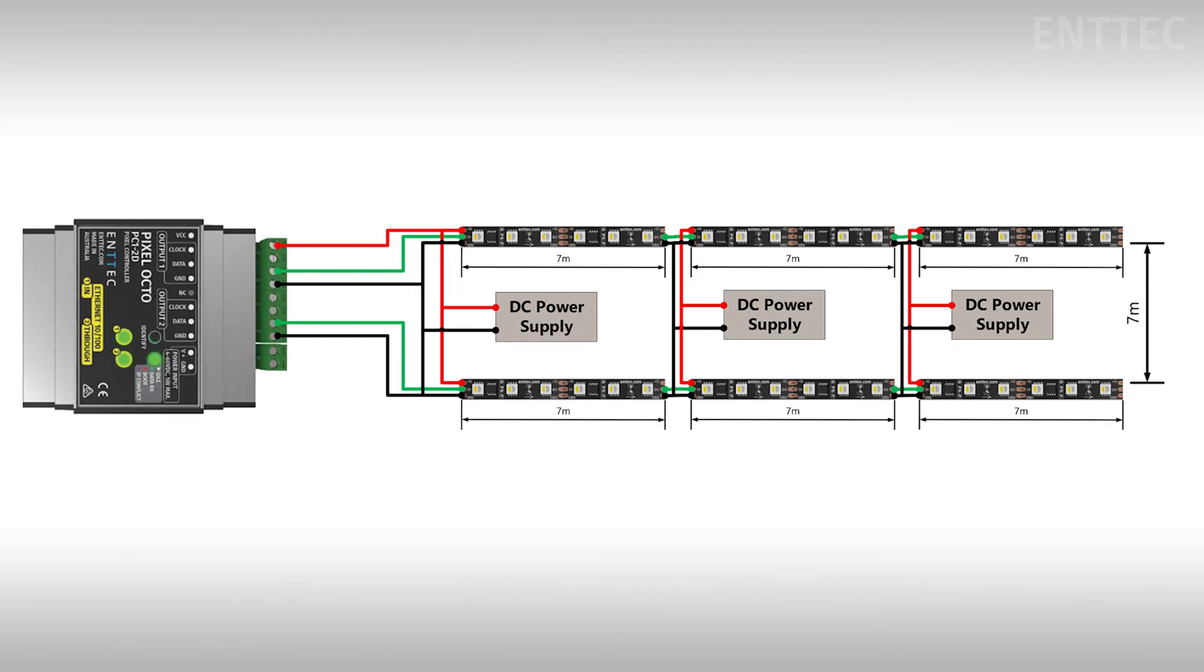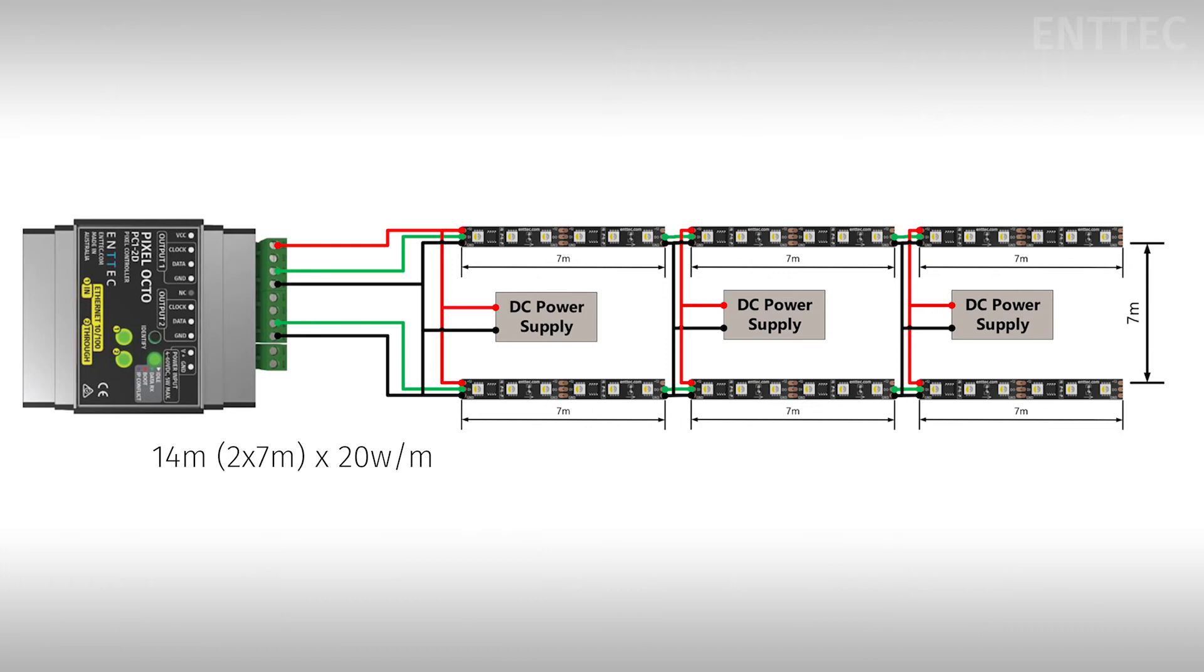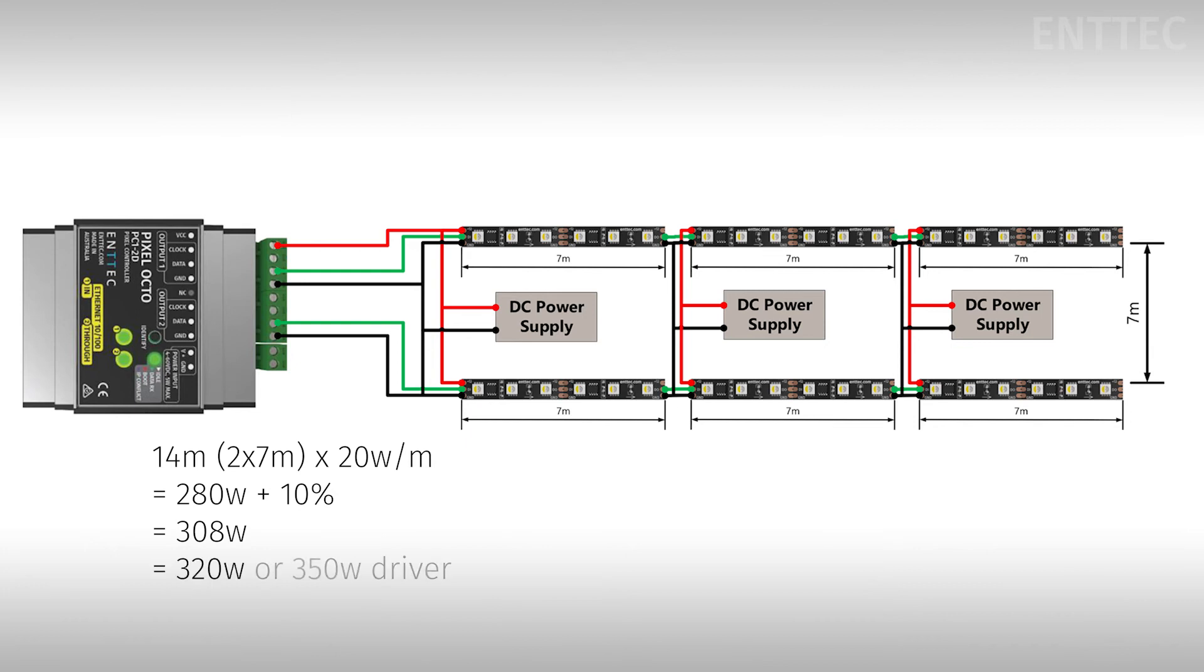Each power supply will be powering a total of 14 meters split across two separate 7 meter lengths. At approximately 20 watts per meter we can calculate that each DC power supply needs to provide at least 280 watts. We'll apply a 10% margin which means we have a power requirement of 308 watts. So we could choose a 320 or 350 watt driver for each power supply as these are commonly available outputs.